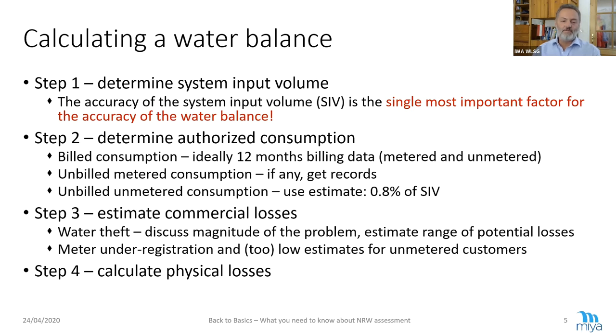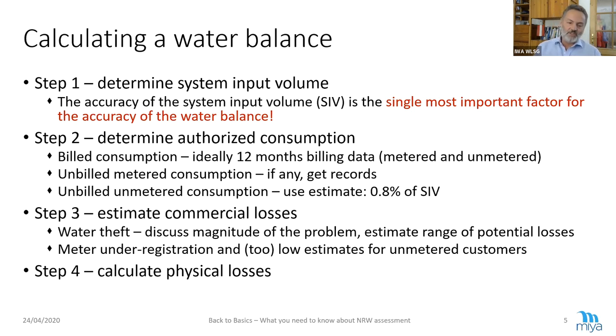Commercial losses — the water theft — we can only estimate. If we would know how many illegal connections, we would do something against it. But we need to estimate the range. Can it be 0 illegal connections? In low and middle income countries, normally the answer is no. Do we have 20%? That is too high. So we say maybe 5%, maybe 10%, and then we give an error range. The meter under-registration — ideally we do meter testing and have numbers. We also need to consider that estimates for unmetered customers can be too low, which comes into commercial losses. At the end, after all of this, we deduct everything from the system input volume and we get our physical losses.